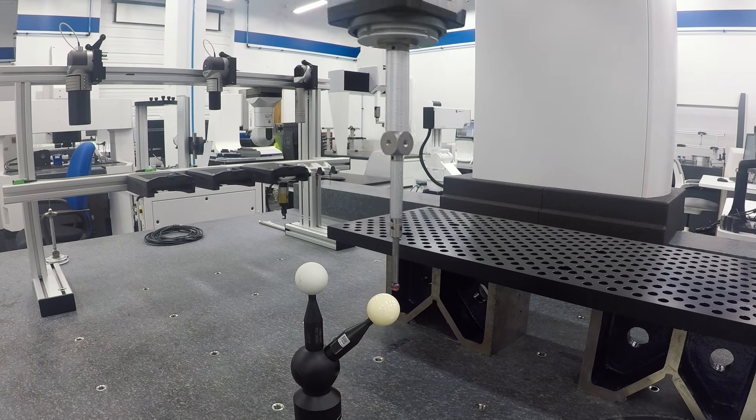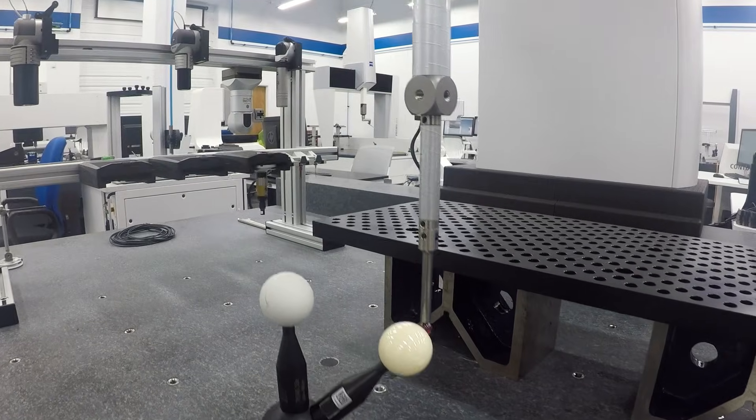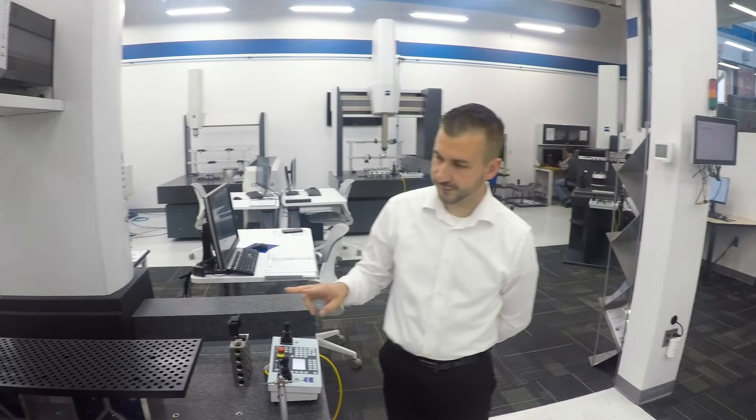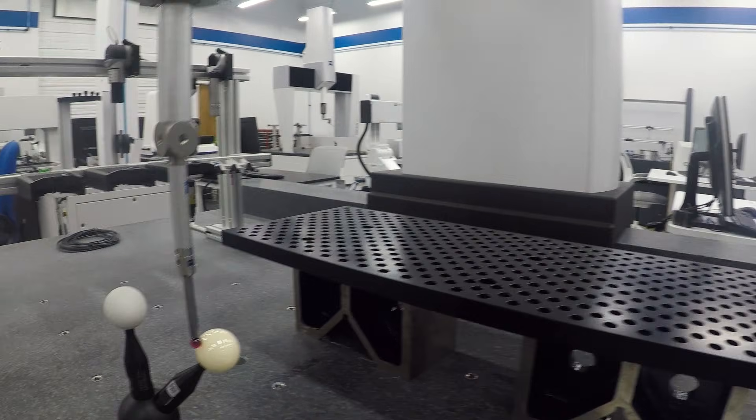What we're doing now is just calibrating a new probe — compensating for the bend at a known pressure, and also at two different pressures. That's awesome.